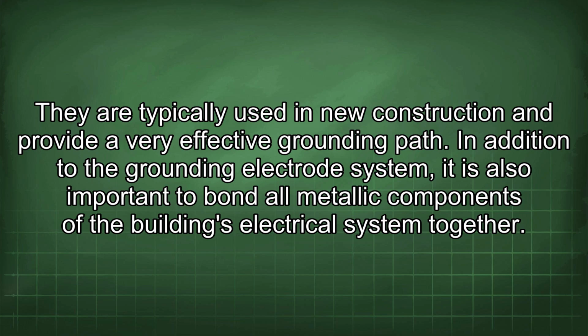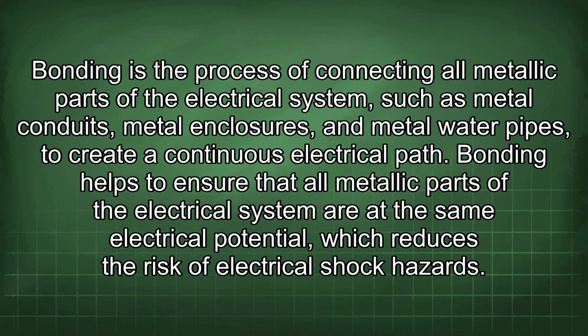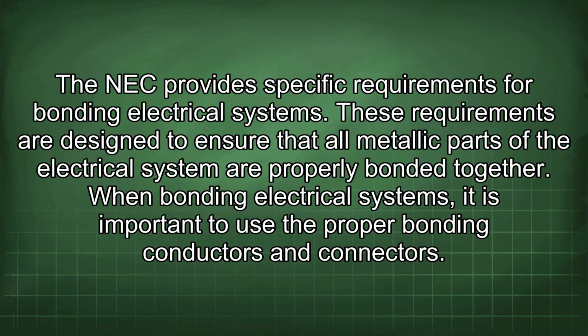In addition to the grounding electrode system, it is also important to bond all metallic components of the building's electrical system together. Bonding is the process of connecting all metallic parts of the electrical system, such as metal conduits, metal enclosures, and metal water pipes, to create a continuous electrical path. Bonding helps to ensure that all metallic parts of the electrical system are at the same electrical potential, which reduces the risk of electrical shock hazards. The NEC provides specific requirements for bonding electrical systems. These requirements are designed to ensure that all metallic parts of the electrical system are properly bonded together.